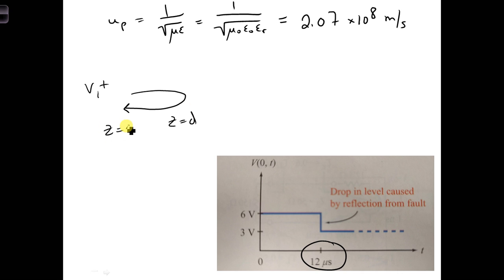so then this would be Z equal 0, then we can write 12 microseconds times U P meters per second is equal to the distance to the fault and back, which is 2D.